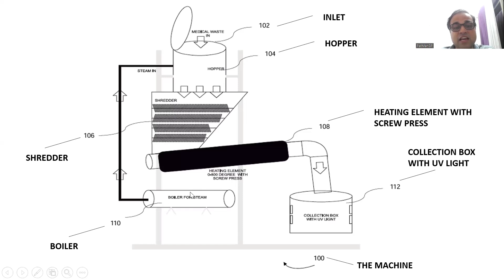Now, while the medical waste is present in the hopper, it is subjected to the process of sterilization, which brings us to the second step: sterilizing the medical waste to kill pathogens and infectious medical microorganisms present in the medical waste. The sterilization is done with the help of the steady flow of steam that is provided by the boiler 110 to the hopper. So the medical waste in the hopper is sterilized by the steam, which is constantly flowing inside the hopper.